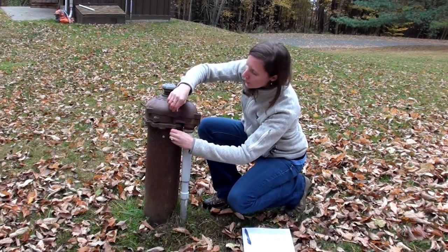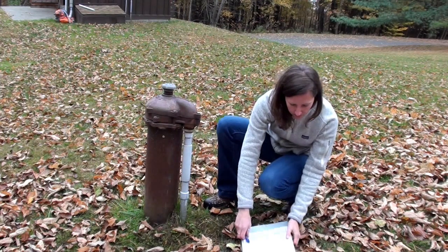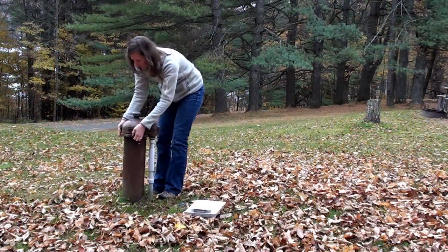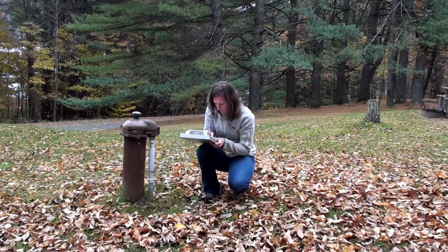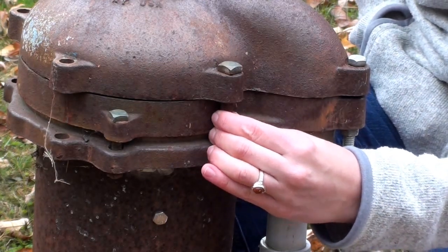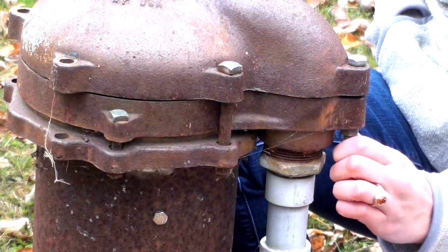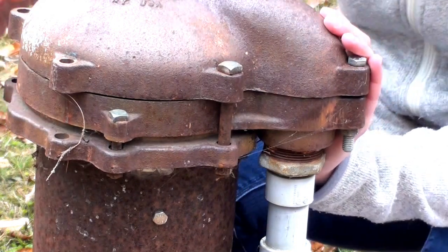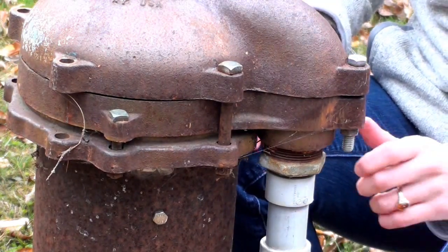For most systems using groundwater, a damaged or faulty well cap can be a common defect allowing contamination into the system. Be sure to check all of the well cap bolts to make sure they're installed and are tight. Make sure the cap is tight on the casing and the cap gasket appears to be intact and working. In this instance, you can see that the well cap is missing 2 bolts and has 2 loose bolts, compromising the sanitary seal of the cap and potentially allowing contamination to enter the system.